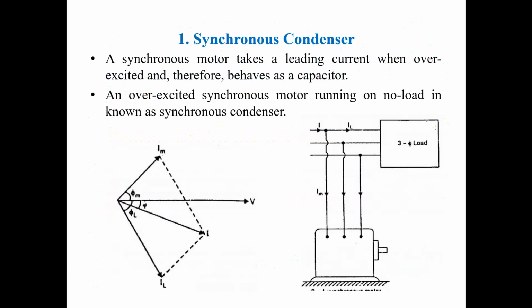Then the one popular application is synchronous condenser. What is a synchronous condenser? Synchronous condenser is nothing but a conventional synchronous motor when it is operated without load, meaning no mechanical load will be on the motor. When it is operated without mechanical load and the operation is in overexcited mode, that means the power factor is leading, and thus it behaves as a capacitor.